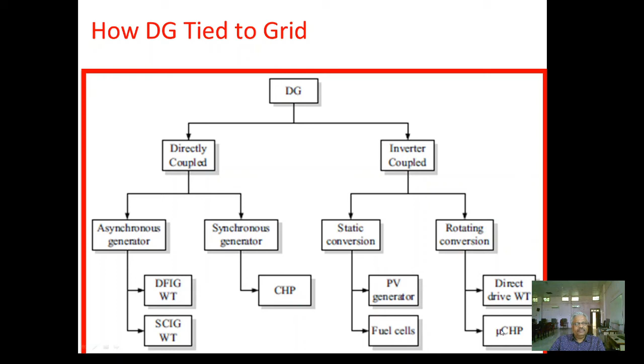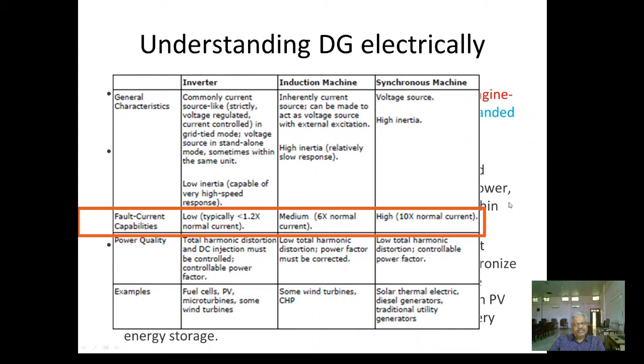Now we'll see how this distributed generation is tied electrically, what the features of these are and what the problems of these are. The general characteristics are given here, that these work as a current source or voltage source. We are not going into detail for this. Our concern is the fault current capability of this interconnection type. For inverter, you will find that the fault current capability is very low, nearly zero, about 1.2 times normal current. For induction machine, it is medium, 6 times normal current. And for synchronous machine, it is very high, 10 times normal current.